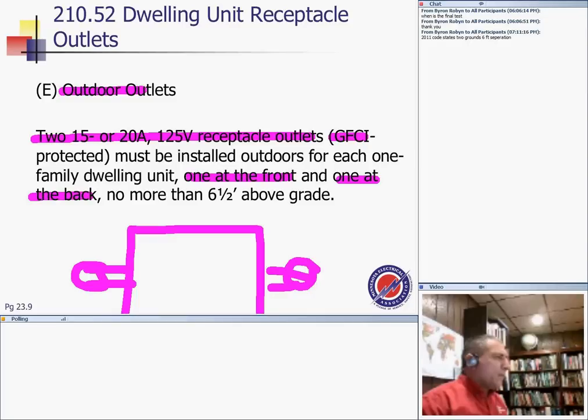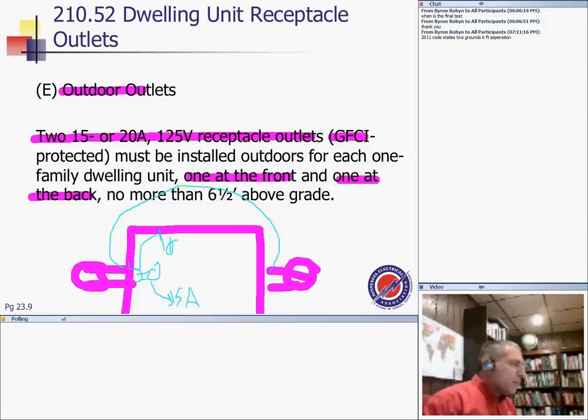Can I power these from the same circuit? May I grab the circuit right in here and feed these, and here's one receptacle here, a third receptacle here, grab them together and feed them from a 15 amp circuit. Is this okay, guys? And by the way, just to make it clear, this area here is a bedroom. So a receptacle in the bedroom and two receptacles outside, fed from the same circuit. Is this okay based on the code, guys? I'm saying, is this okay based on the code? How about a green check? Yes. No, don't hesitate. Give it a shot.